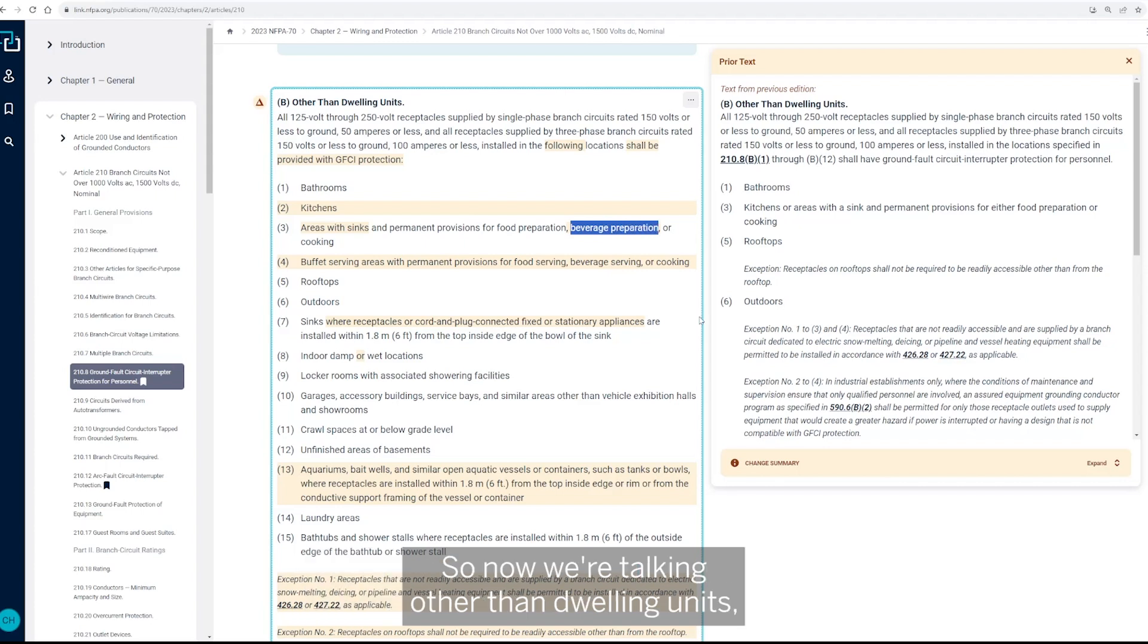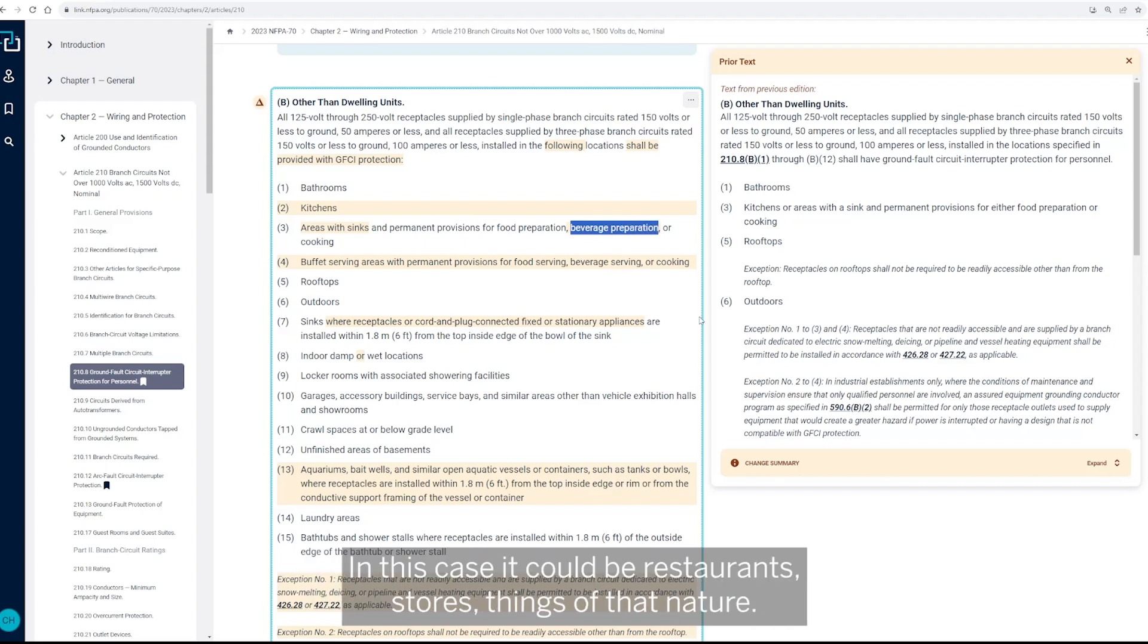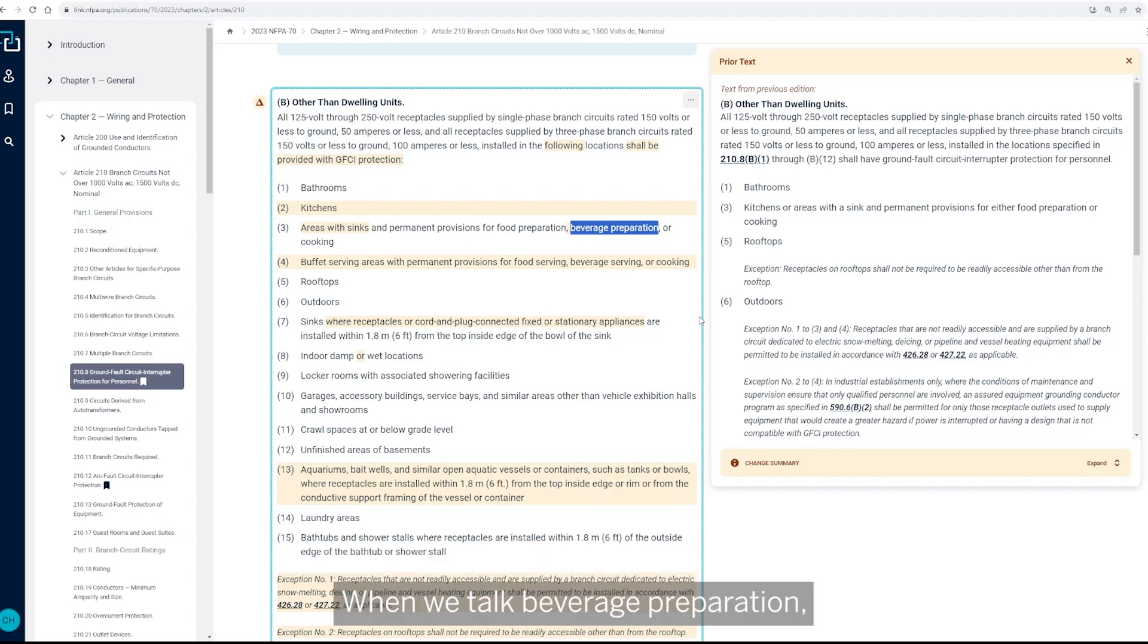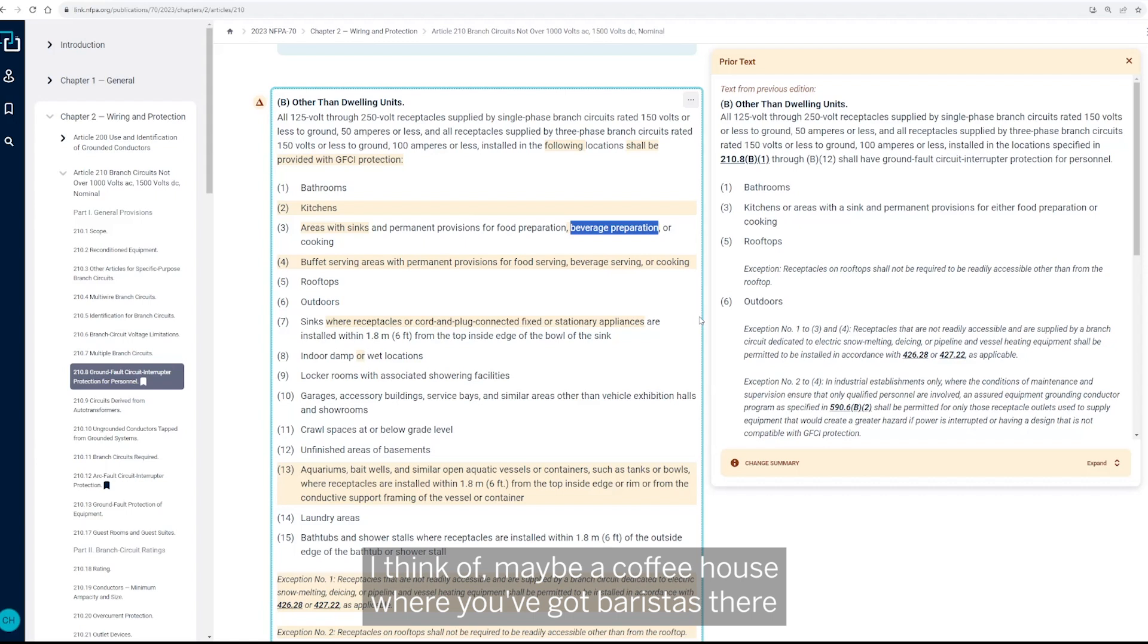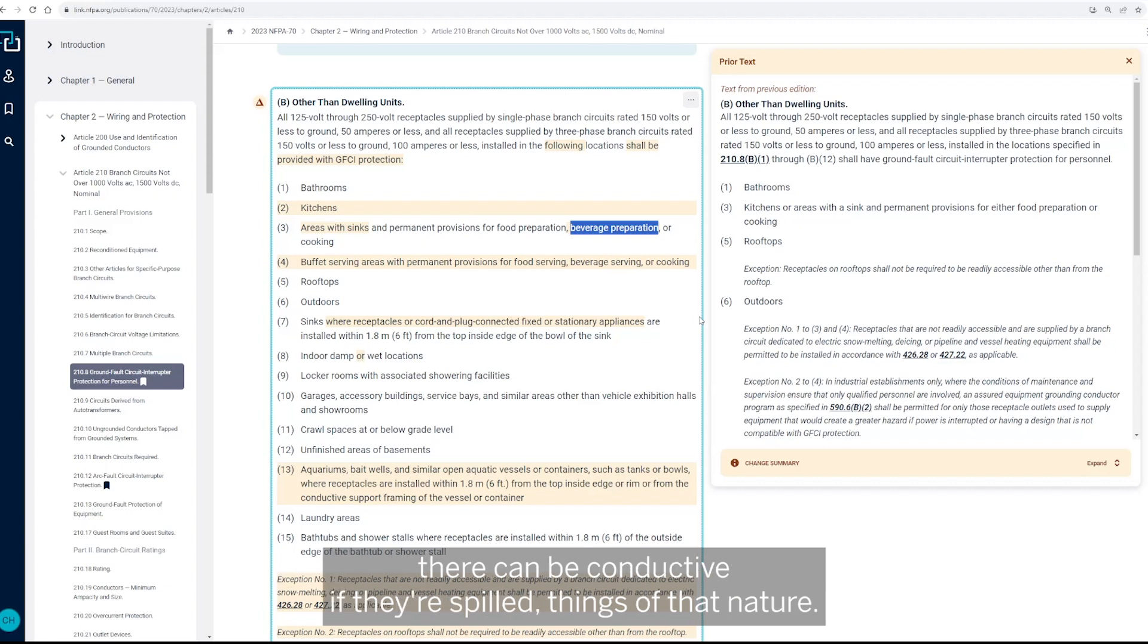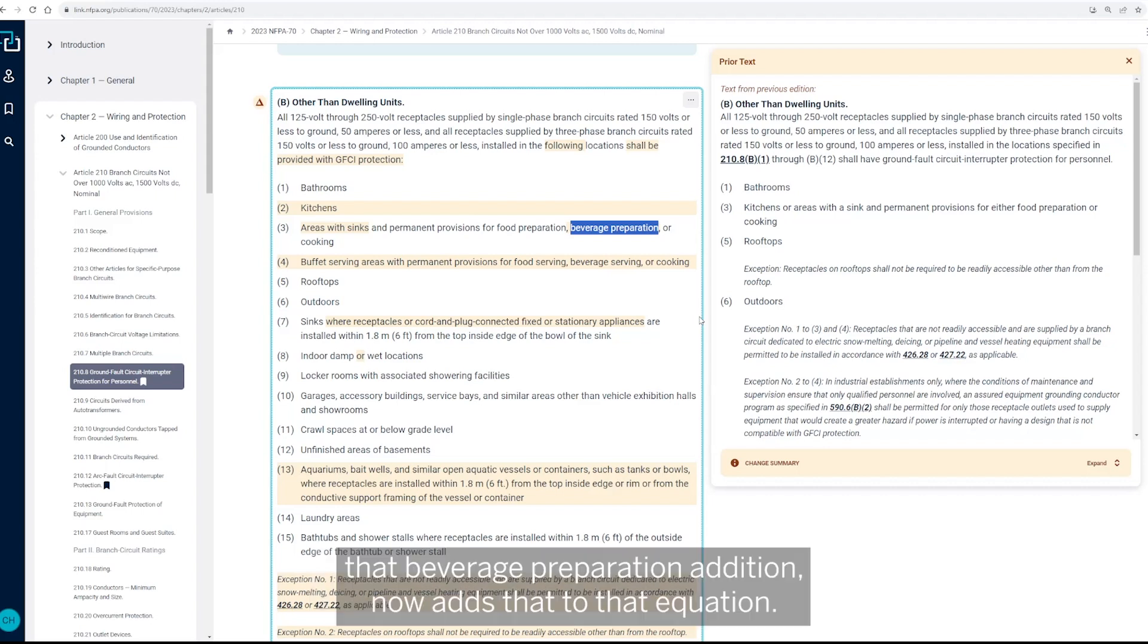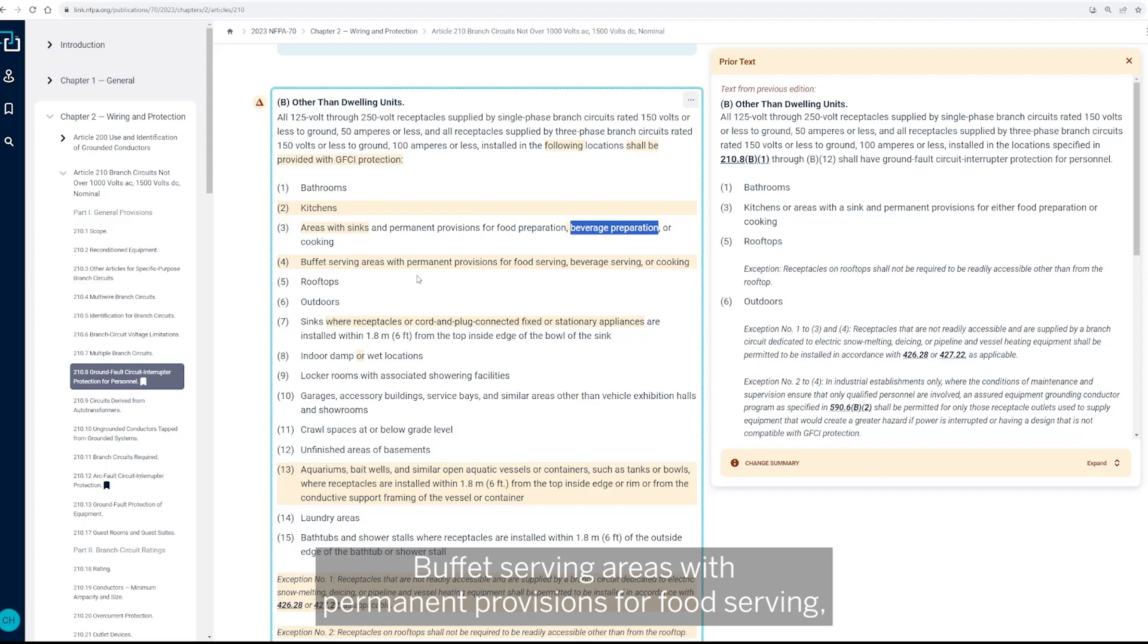but they've also added beverage preparation to that. So now we're talking other than dwelling units, we're talking commercial properties. So in this case, it could be restaurants, stores, things of that nature. So when we talk beverage preparation, I think of a coffee house where you've got baristas there that are making beverages. Certainly those liquids that are there can be conductive if they're spilled, things of that nature. So whereas the GFCI protection wasn't required before in those applications, that beverage preparation addition now adds that to that equation.